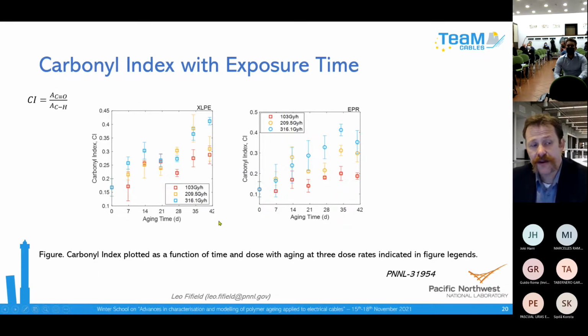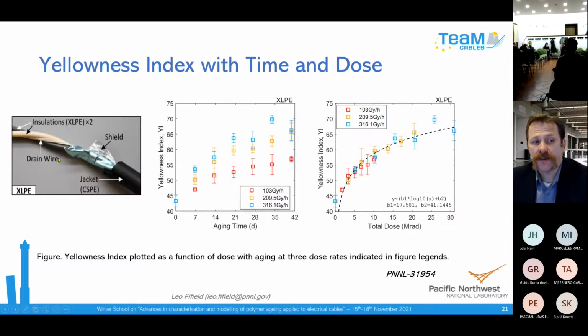We measured carbonyl index. This is a Fourier transform infrared spectroscopy technique to look at the formation of carbon-oxygen bonds on the surface of the polymers. We saw a trend with dose. For one of the insulations we measured, the XLPE was a white-colored insulation. So an area that we've developed in the last few years that's been fruitful is quantifying color change. It works better for light color materials than dark color materials, but color change actually tracks pretty well with polymer aging. So we measured the color change of this insulation with exposure, and it's a very surface sensitive technique, and we saw a dose dependence. It wasn't as linear as some of the others.